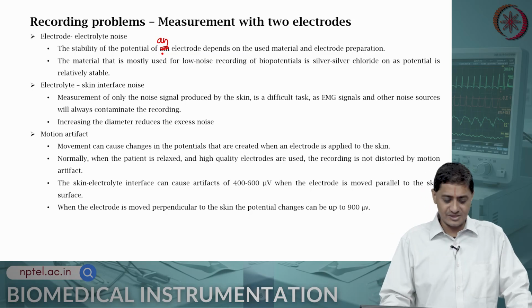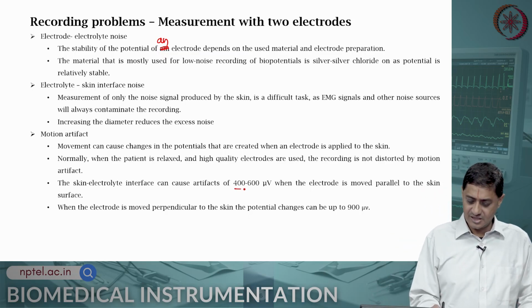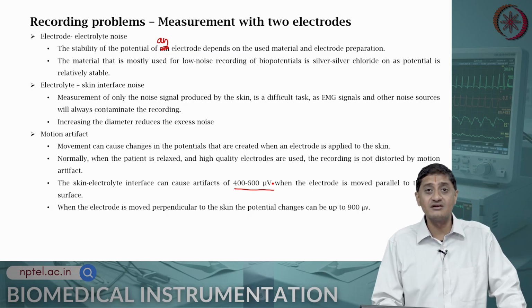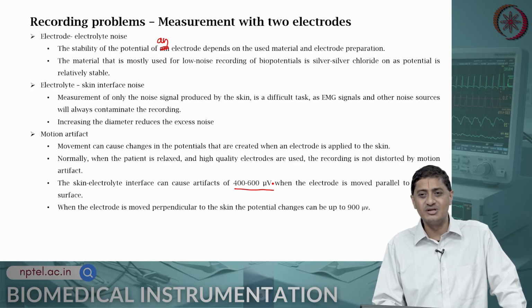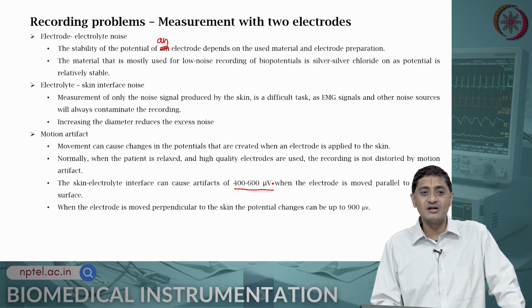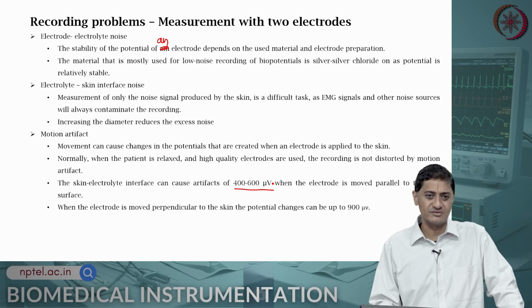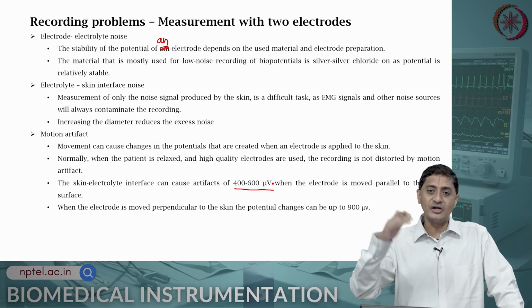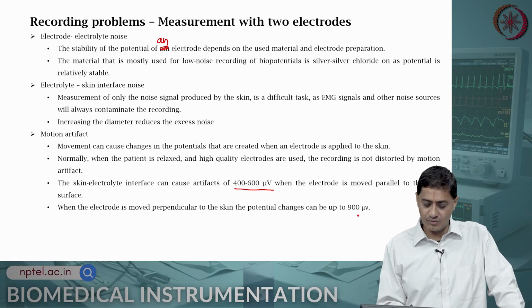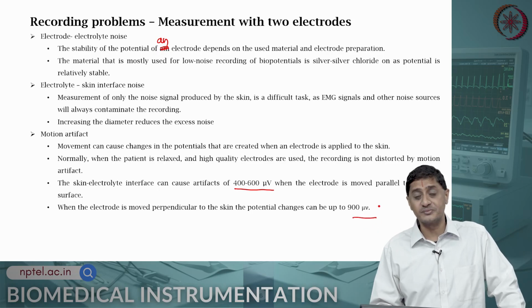So, artifacts in the skin electrode can sometimes be of the order of several hundreds of microvolts, close to millivolts. When the electrode is moved parallel to the skin, then this happens quite often. When the electrode is moved perpendicular to the skin, then the voltages can be as high as 1 millivolt, right.